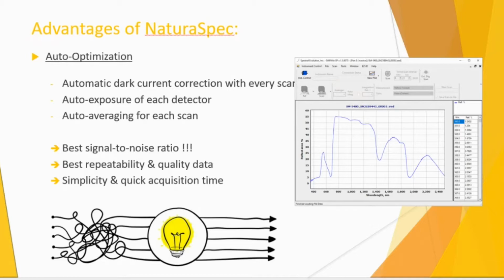So you can either input this manually if you want, let's say, 20 averages for every scan, or you can let the software do that for you and optimize it directly. Most customers we have use the auto averaging feature because it really makes life a lot simpler, and then you make sure that you get your optimum exposure and averaging time for every single scan. All those little optimization features make the NaturaSpec the instrument with the best signal to noise ratio on the market.